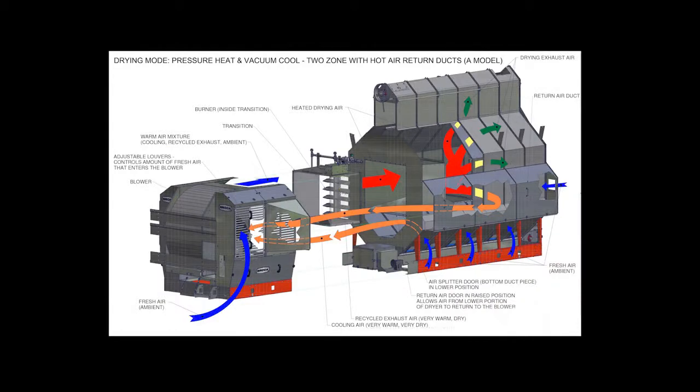In the pressure heat vacuum cooling drying mode, the dryer draws warm air from the grain cooling section and recycles it through the fan. This air is mixed with fresh air being pulled through louvered openings at the front of the dryer next to the fan. These two volumes of air are then mixed and passed through the burner into the grain basket.